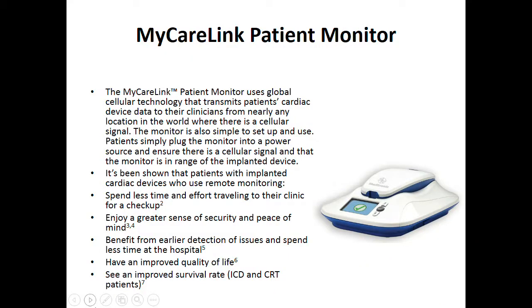And that's another reason the batteries last so long, because you've got it right down inside the heart tissue. Once the pacemaker is implanted, we follow it up with a little device that Brandy can pass around and show you. It used to be that you'd have to come to the office every 3 to 6 months, and we would have to physically put the programmer on and check the pacemaker. Nowadays we have what's called home monitoring or CareLink, and you can put this little handy device next to your bed and it'll read your pacemaker or defibrillator and transmit the data by cellular means to us, where we can analyze it and follow it up without you actually having to come in. So it really decreases the amount of physical time for follow-up of pacemakers these days.